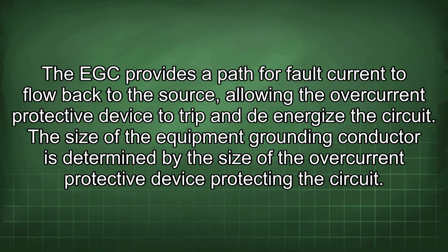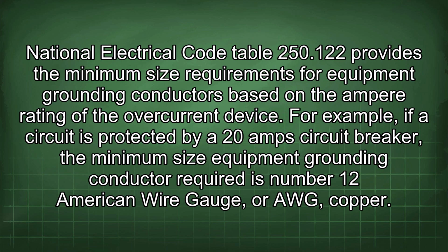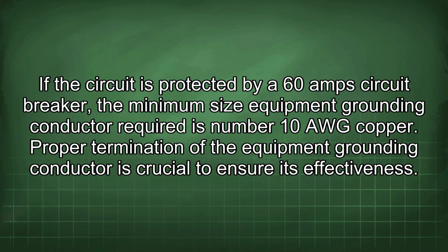The size of the equipment grounding conductor is determined by the size of the overcurrent protective device protecting the circuit. National Electrical Code Table 250.122 provides the minimum size requirements for equipment grounding conductors based on the ampere rating of the overcurrent device. For example, if a circuit is protected by a 20 amp circuit breaker, the minimum size equipment grounding conductor required is number 12 American wire gauge, or AWG, copper. If the circuit is protected by a 60 amp circuit breaker, the minimum size equipment grounding conductor required is number 10 AWG, copper. Proper termination of the equipment grounding conductor is crucial to ensure its effectiveness.